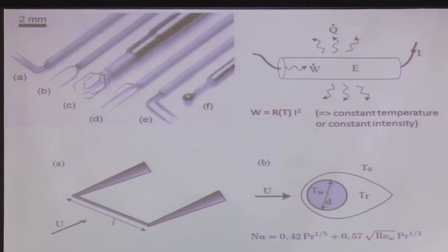You have a wind tunnel which is very well designed, where you know the velocity for different fan velocities, and then you calibrate what the velocity is for each resistance. You have a curve like this, and when you measure the resistance, you will have the velocity of the fluid at that point, with the calibration.